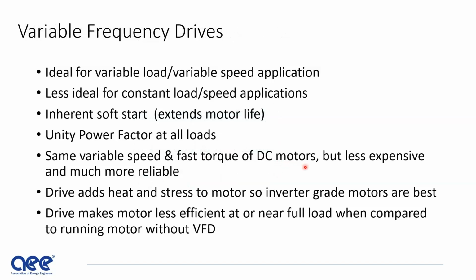Variable frequency drives are ideal for variable load, variable speed applications, unless you have a serious power factor issue that you're trying to solve and you can't change the motor. It's less ideal for constant load, constant speed applications. There is inherent soft start.